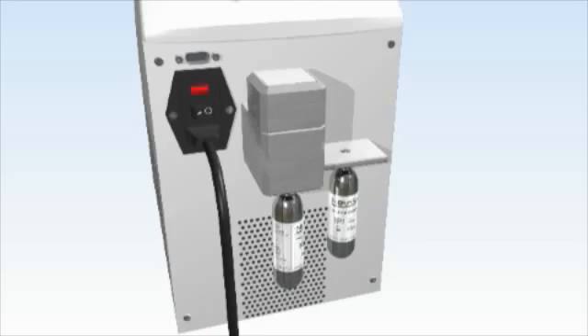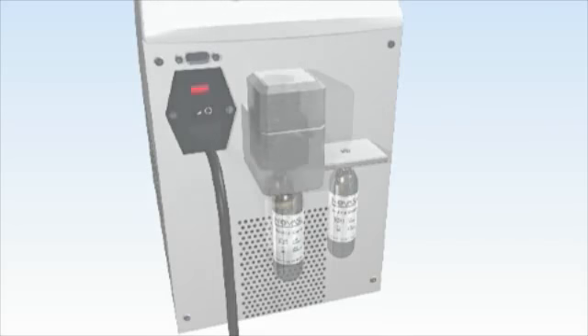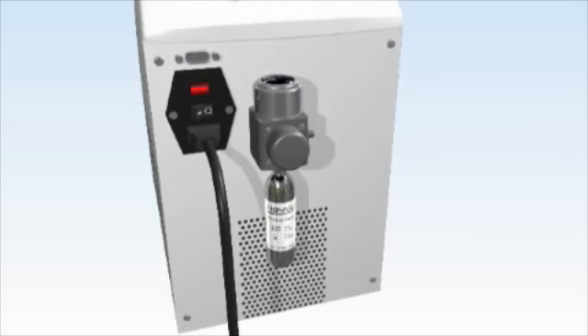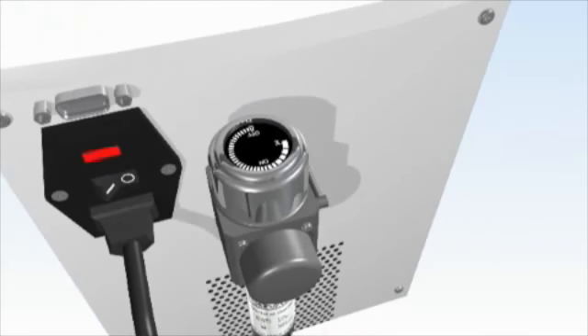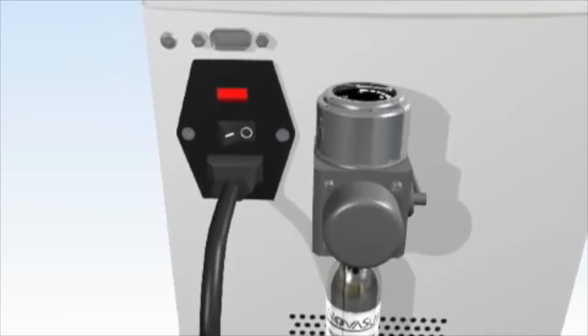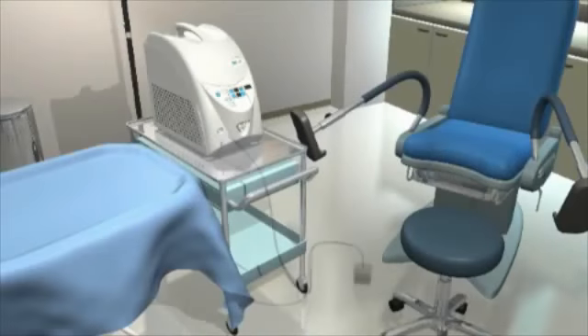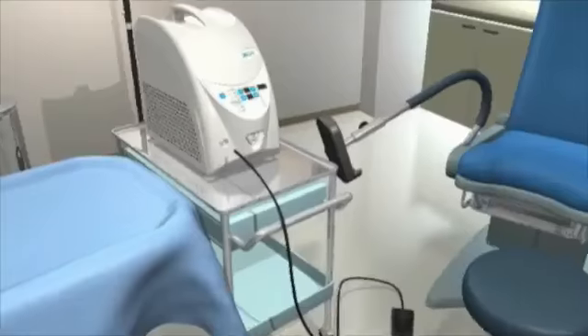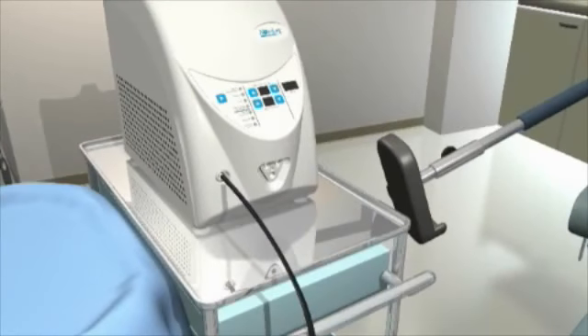Screw the CO2 canister into the regulator on the back panel of the controller until tight. If your controller is equipped with a CO2 regulator knob, turn the knob clockwise until the word high is in line with the silver arrow on the regulator. Press the toggle switch on the back panel of the controller to the on position. Connect the foot switch to the appropriate port on the front panel of the NovaSure RF controller.